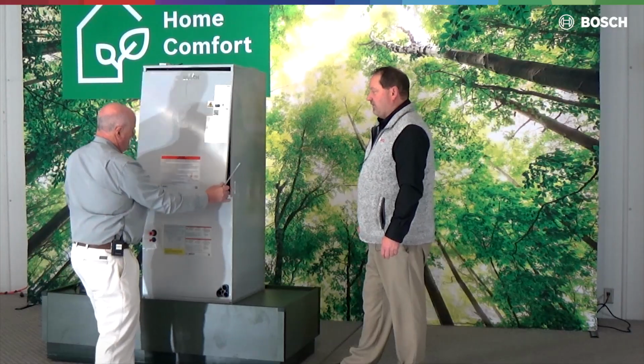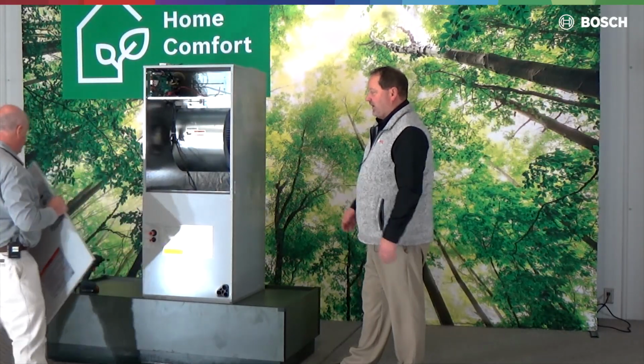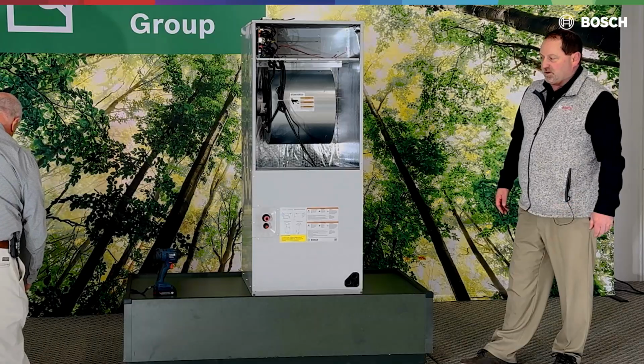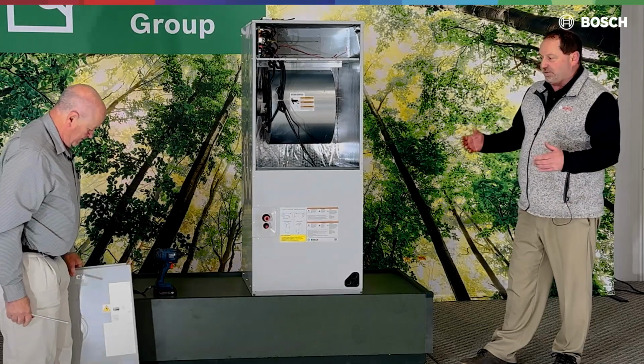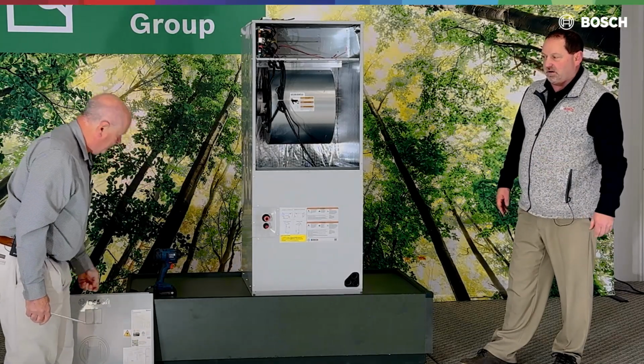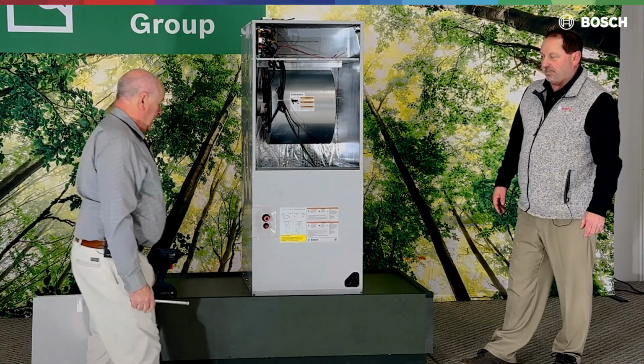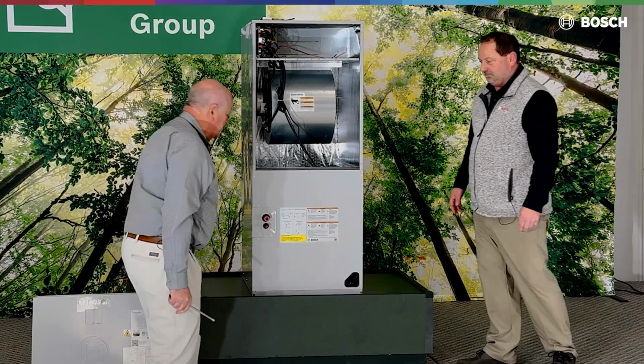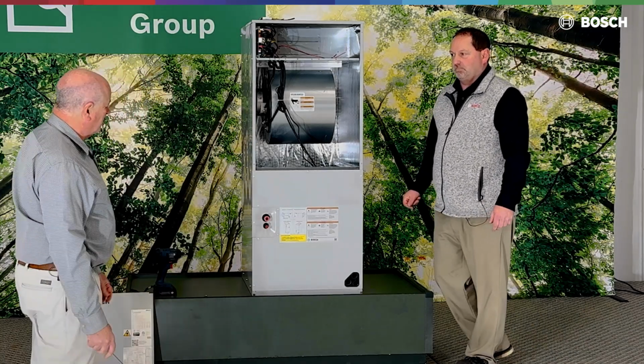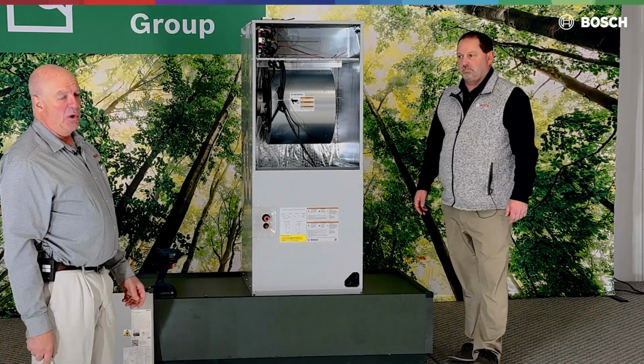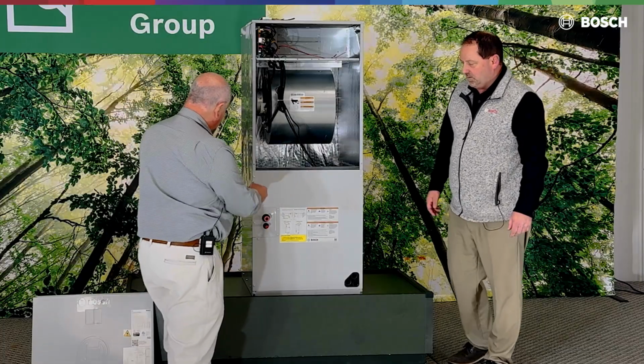So when we talk about upflow, converting to downflow and horizontal, is the procedure for horizontal and downflow the same, or is there a couple of things that need to go a little bit differently into that? Well, one of the things for downflow is the unit has to be flipped upside down. And for us to flip that unit upside down, we got to pull out the coil to make that happen. Okay. Let's go ahead and expose the coil.